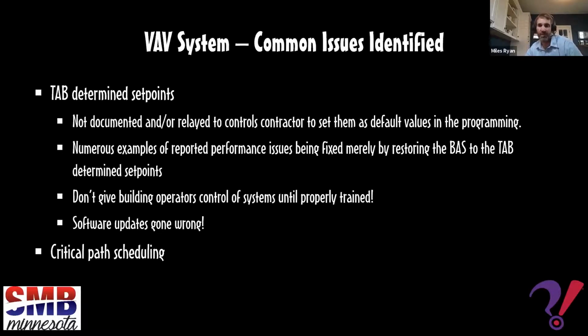So that kind of goes along with, don't give building operators control of these systems until they've been properly trained on the control system and what set points and what set point adjustments would be acceptable and which adjustments would not be acceptable. So along those lines, there's opportunities for information to be lost by the automation system if it crashes, and the TAB professional is often very instrumental in getting that information back to them. So I'll let Mark kind of talk to that last one, the software updates gone wrong.